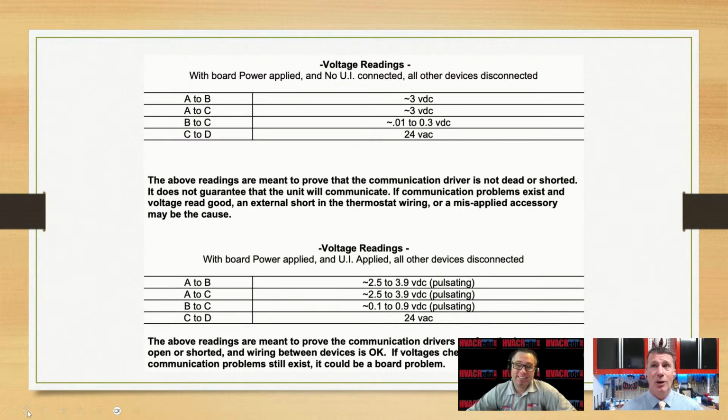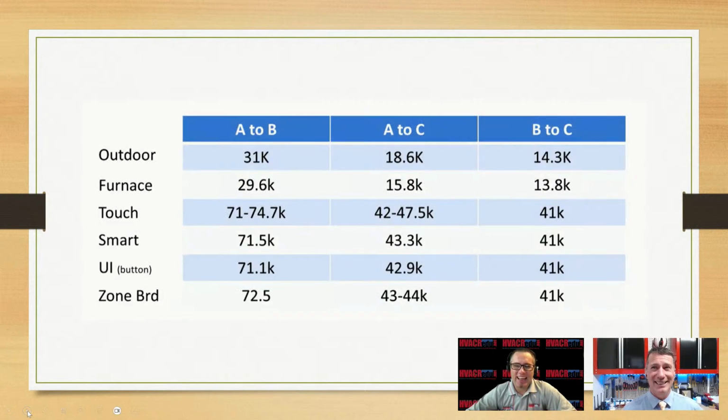The only thing that I don't see in many of these, except for the very first one, is a measurement between A and B, which would be our bias voltage. So I need to round up some friends and get in some of their labs and ask, all right, what's the bias voltage on every one of these manufacturers? Because I've got a feeling they all operate under the same principle, that if I have a certain bias and it's below this, I can't communicate well.